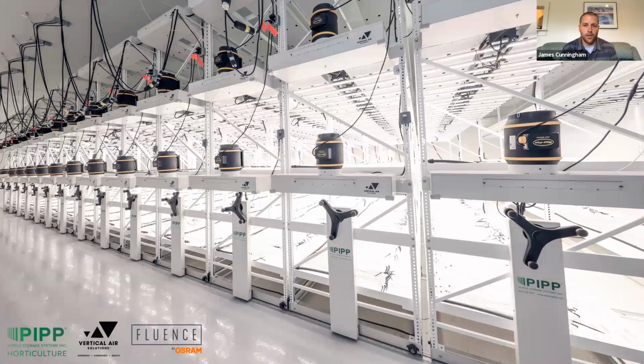So we figured out throughout the process that putting that filter underneath the fan takes the direction of the fan out of it and allows for even diffusion of the air into both ducting runs and better pressurization and balancing front to back. So you can have a single fan, as in this veg solution, that will add a less than 3 CFM variance front to back in airflow. So we also have other configurations as well for any velocity that you would want to achieve in this space.